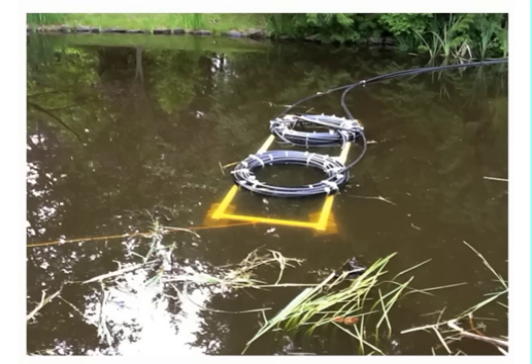Here's an example of that pond loop. You can see it's floating nice and evenly with those blocks, and the reason it's still floating is we still have air in those coils. Trust me, when you attach an appropriate flush cart to the ends of this connection at the heat pump and introduce the fluid, this bad boy goes right down. If you've spread that weight out evenly, it's going to go down very nicely and very evenly.